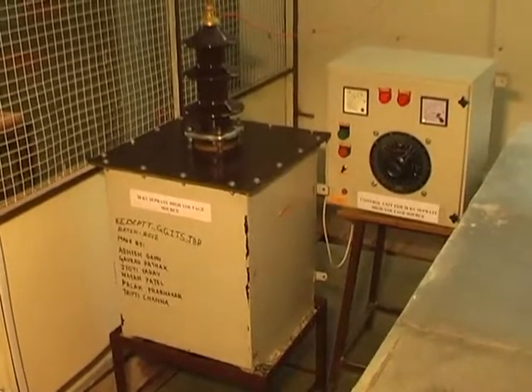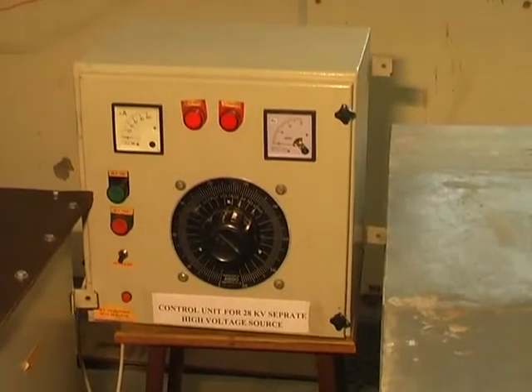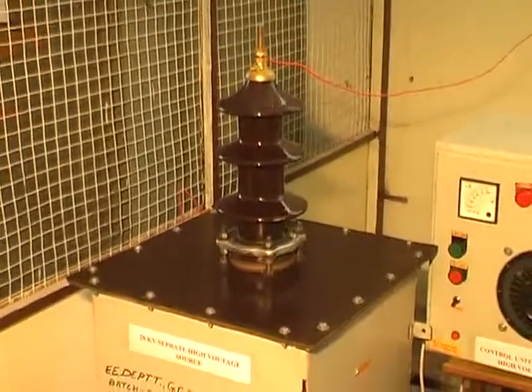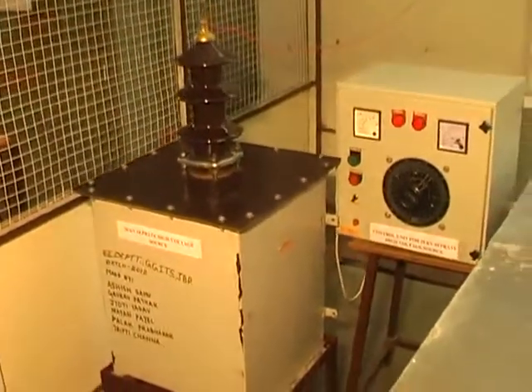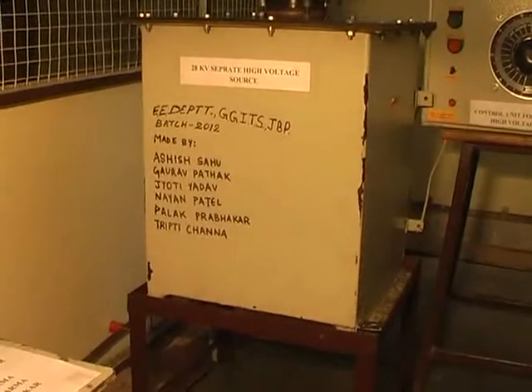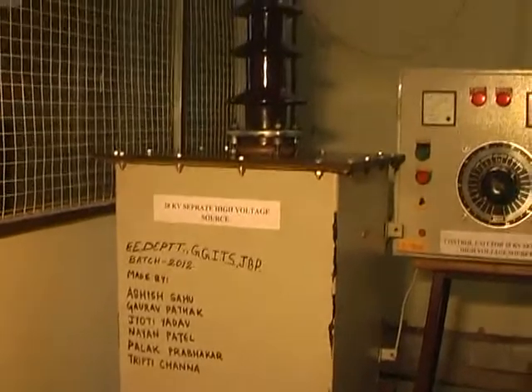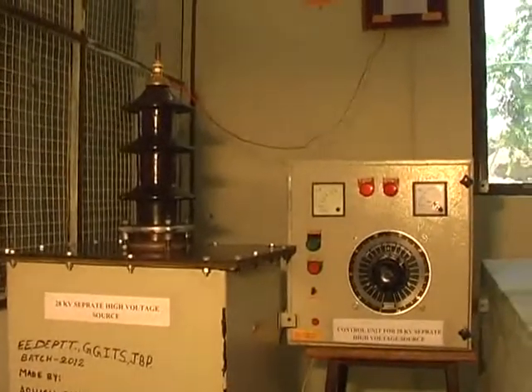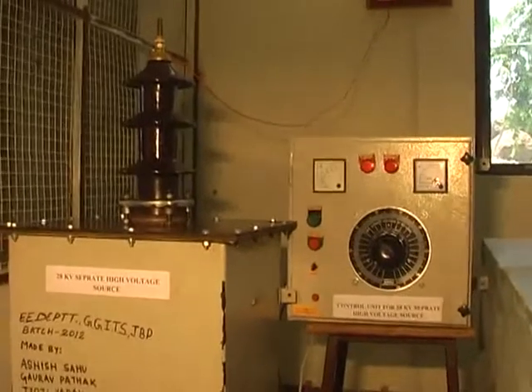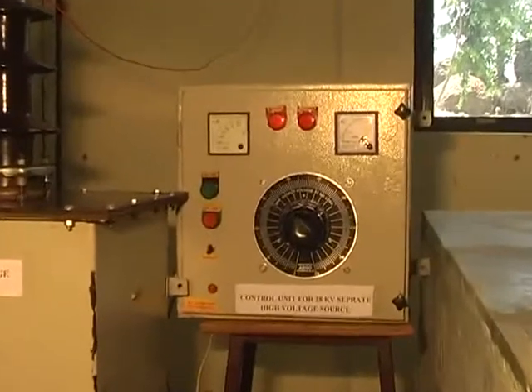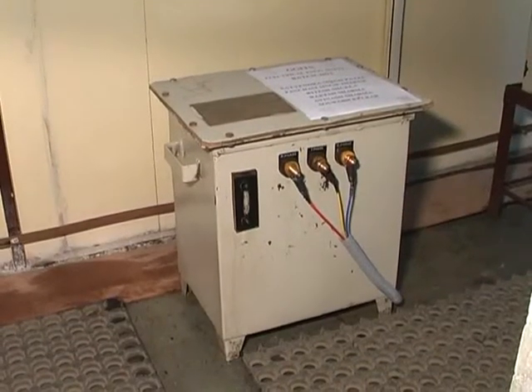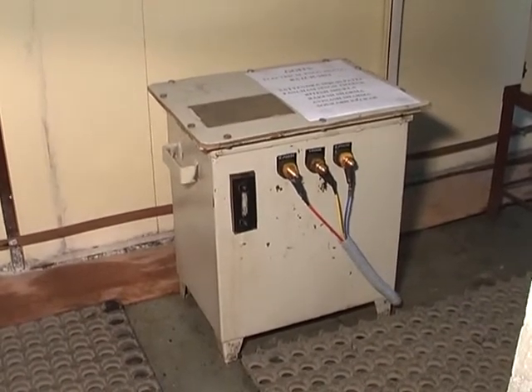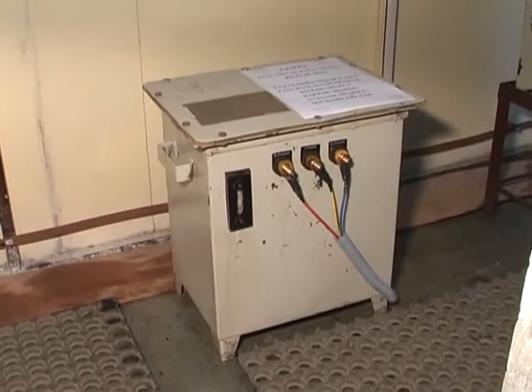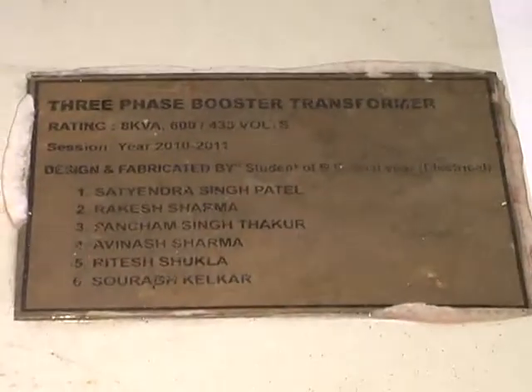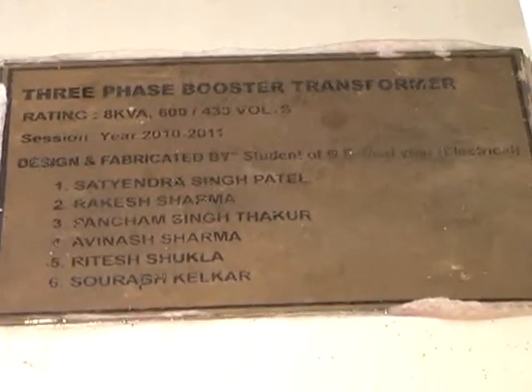This is 28 kV voltage source which is required for testing of 11 kV transformer as per IS 2026 requirement. This is the main transformer which develops single phase 28 kV, and this is the control unit for this separate source testing setup. This is voltage booster which is required for measurement of load losses and percentage impedance of the power transformer. This has been designed and fabricated by the batch of the electrical engineering department.